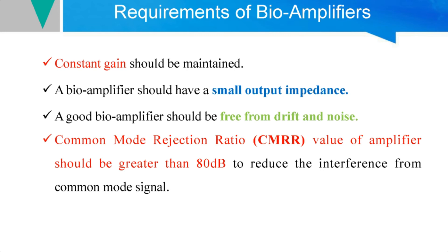The common mode rejection ratio (CMRR) should be greater than 80 dB in order to avoid noise and interference. To summarize the major requirements: there should be isolation to prevent shock, high input impedance, low output impedance, freedom from drift and noise, and a constant gain maintained throughout the amplifier.